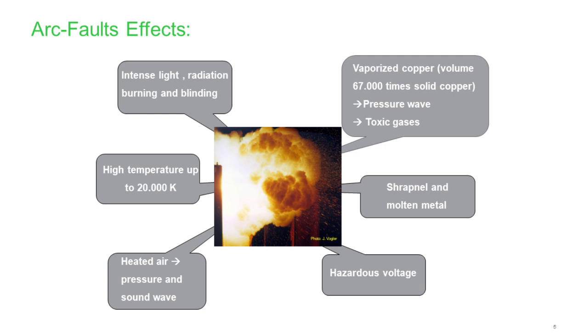Let's look at some effects of the arc. When we have an arc incident, there will be intense light, radiation, burning, and blindness. We will have vaporized copper or vaporized material, whatever is in the enclosure. With a very high volume, it will cause very high pressure and toxic gases. We might have shrapnel and molten metal, and high voltage will definitely be present. Heated air, pressure, and sound waves — and finally, very high temperature, up to 20,000 Kelvin.